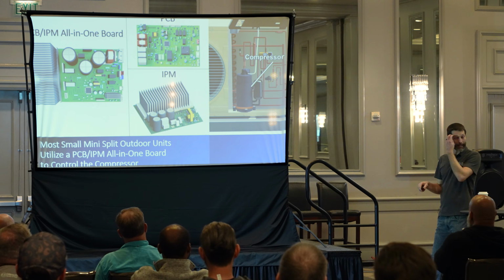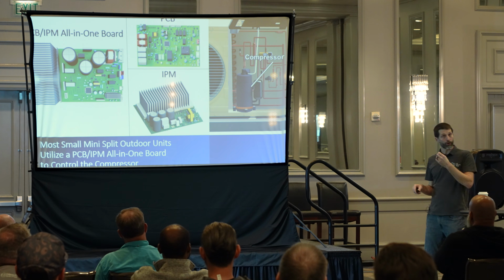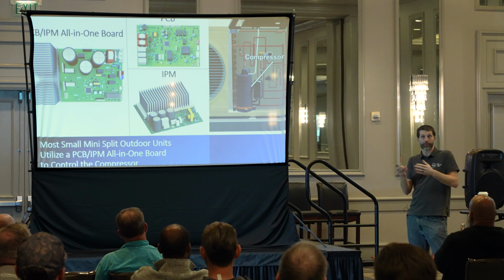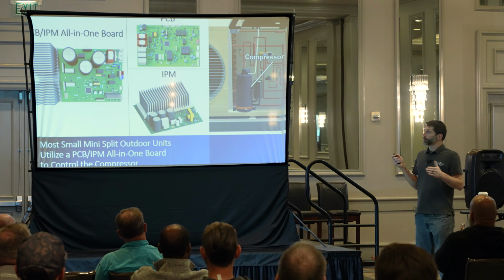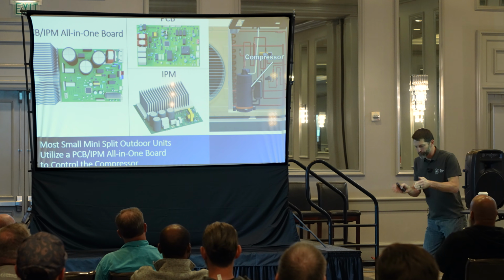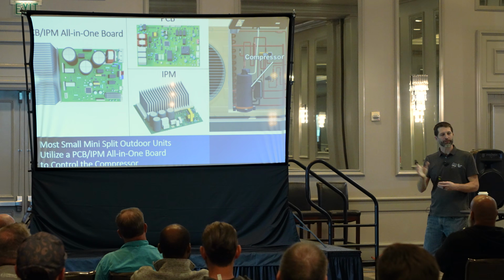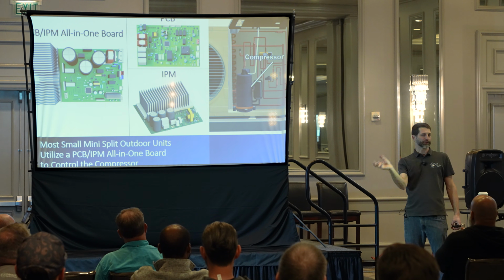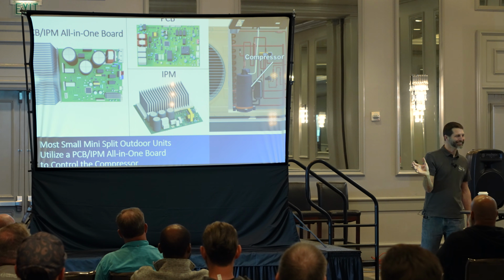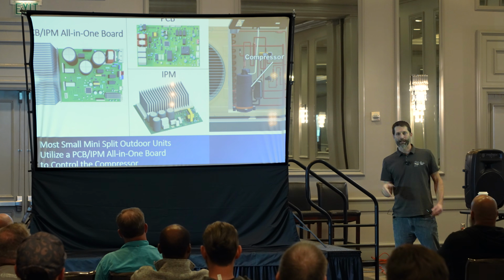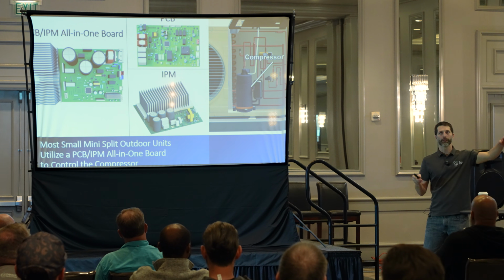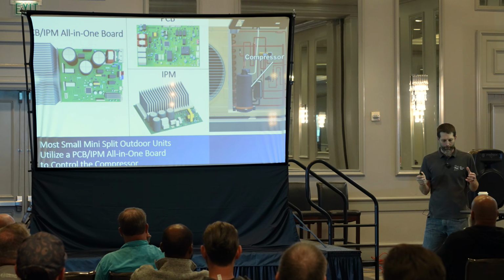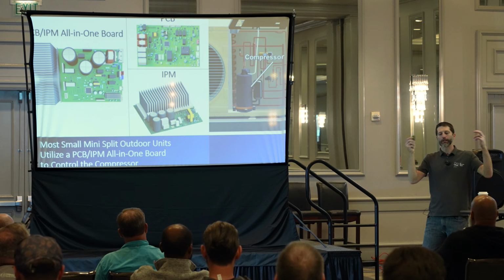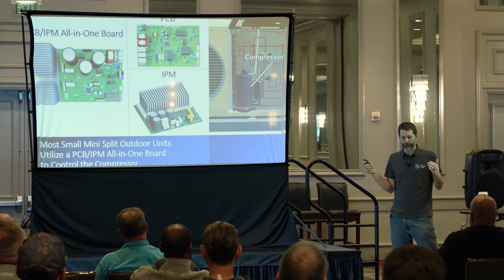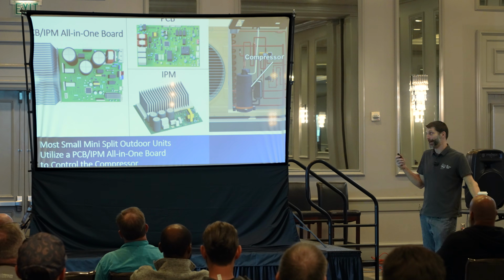That's when it's happening. If you want to put your multimeter on two of the four wires, like the common wire and one of the four wires on the EEV, the 12-volt pulses going to that EEV are happening so fast that you can't even measure it with your multimeter. I'd love to give you better news, but I don't have it. That's why I'm saying, break the systems down so you at least know how to operate them, how they work, and what's going on, so you know what's happening to diagnose a system that's wrong or bad.